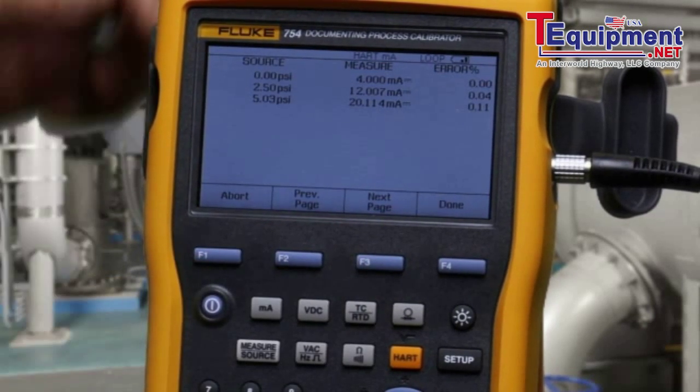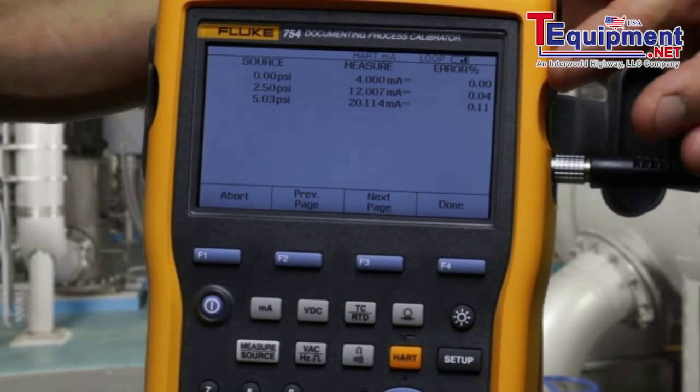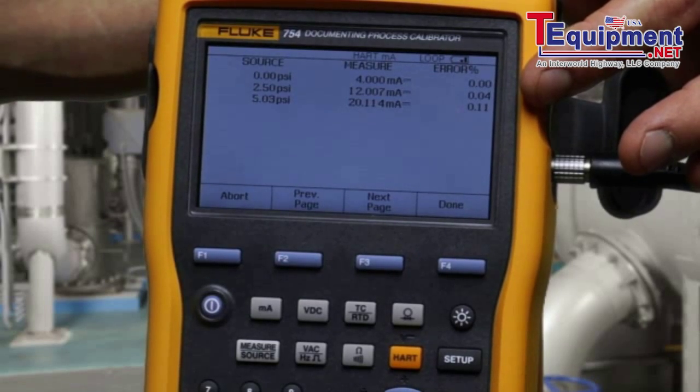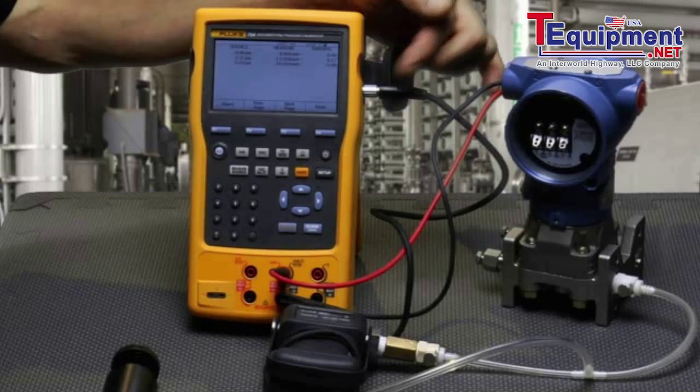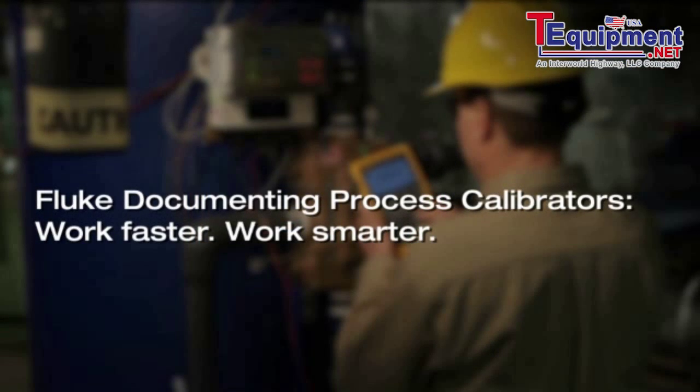Test is complete. You see the applied pressure and measured milliamp. In this case, all the errors are less than 0.25% and the test passes. And that is how you calibrate a Rosemount 3051 HART Smart pressure transmitter using the Fluke 754 documenting HART process calibrator.